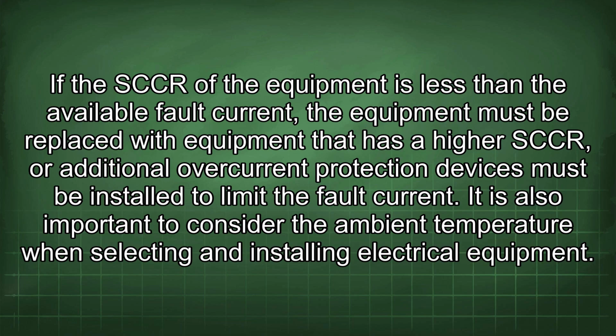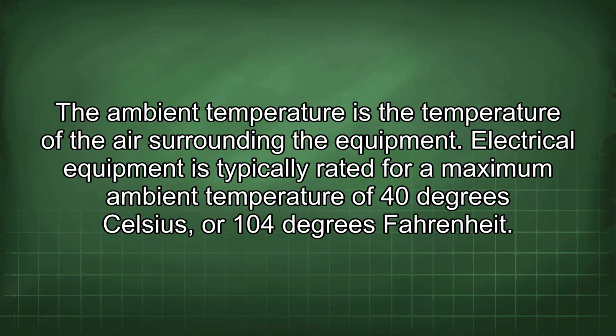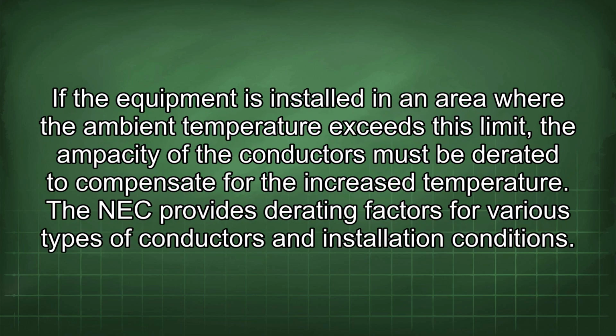It is also important to consider the ambient temperature when selecting and installing electrical equipment. The ambient temperature is the temperature of the air surrounding the equipment. Electrical equipment is typically rated for a maximum ambient temperature of 40 degrees Celsius or 104 degrees Fahrenheit. If the equipment is installed in an area where the ambient temperature exceeds this limit, the ampacity of the conductors must be derated to compensate for the increased temperature. The NEC provides derating factors for various types of conductors and installation conditions.